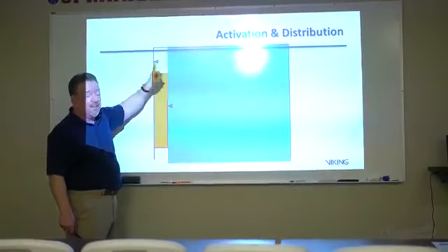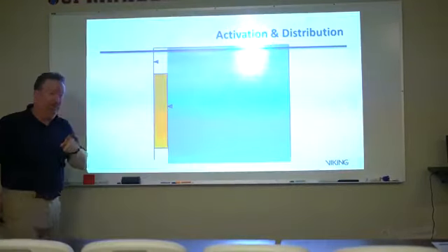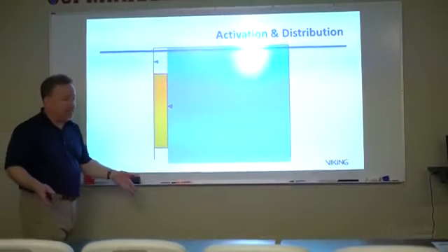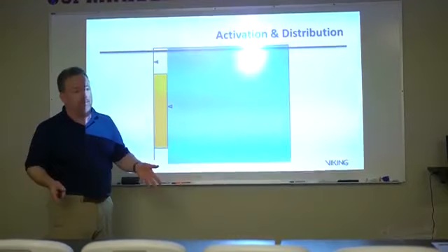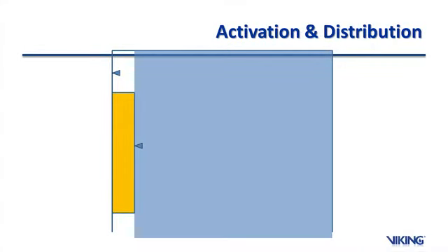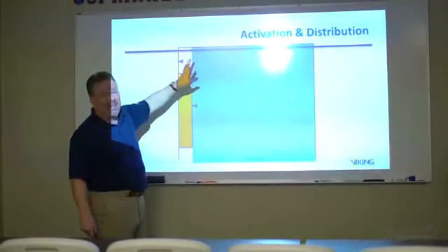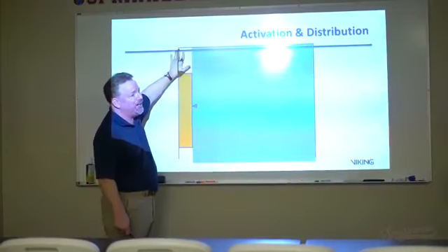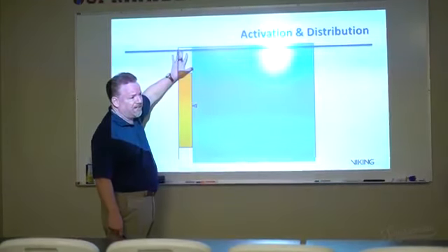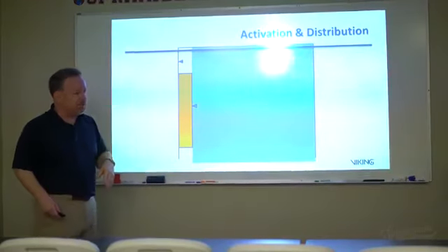back in there. The other thing is that nowhere in the standard ever did it say that you have to get 0.1 or the density over the entire area that it's required. It never really said anything about little shadow areas like this. In fact, we've had obstruction rules in the standard for decades. Okay, understanding that in some cases you got obstructions to spray pattern that might actually affect the overall spray pattern getting to a particular spot.